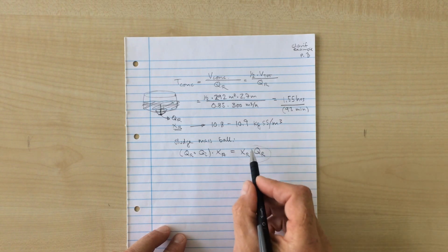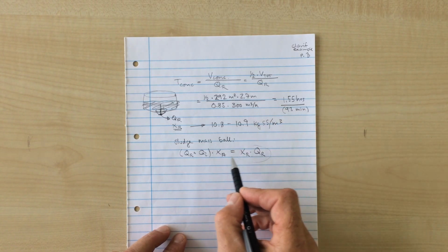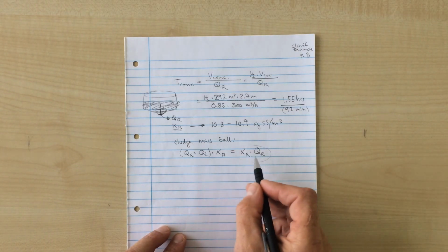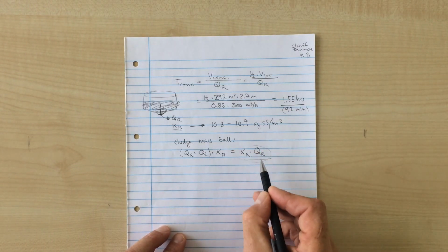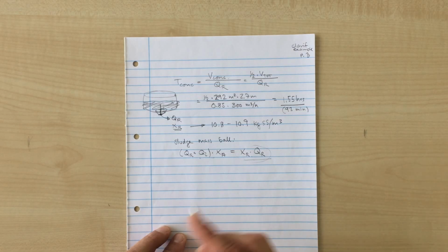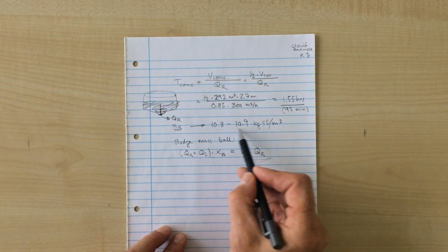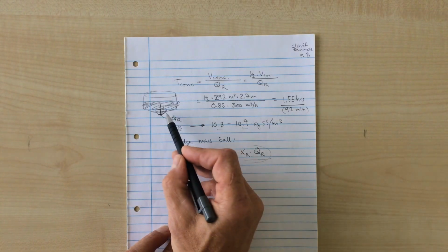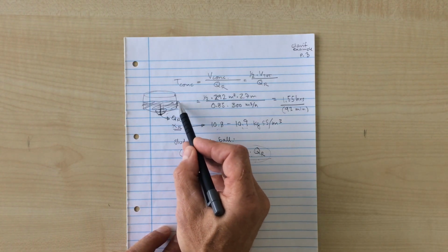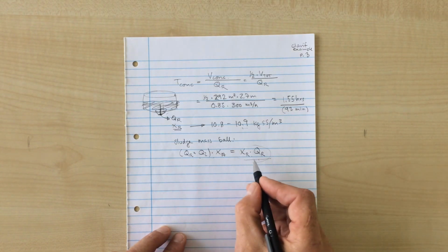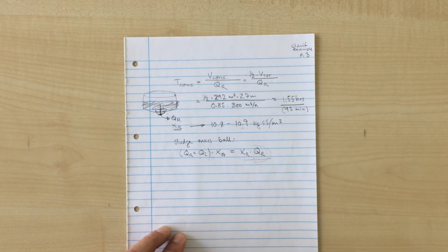If I'm not, with this concentration, able to pump back as much as I have in the inlet, I'm in trouble. So looking at things with these numbers, this number over here should be at least as big as this. If it's bigger over here, that's okay. That just means that I don't need to concentrate up to the maximum. I could have a sludge level that's less than 50% and hence a smaller concentration time. So I'm going to see if the number over here is bigger than the number here.